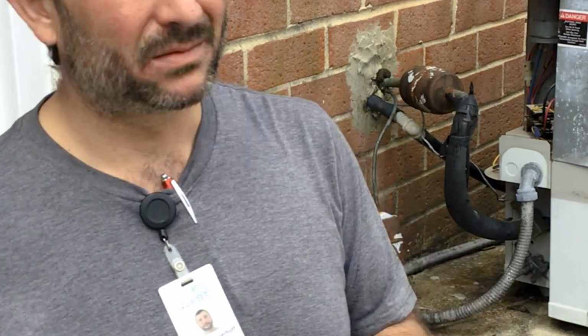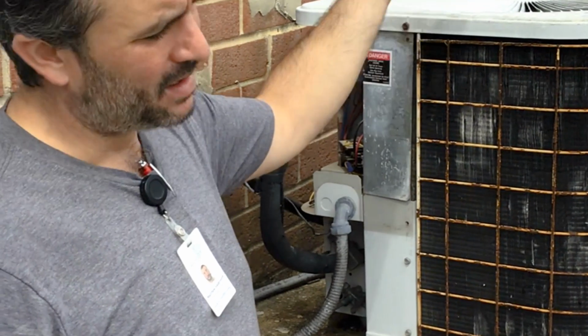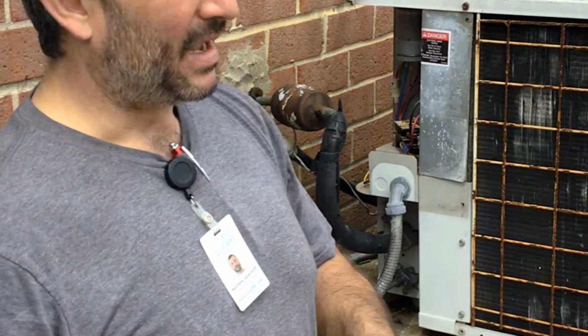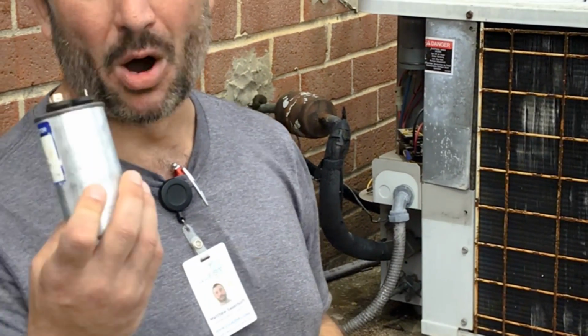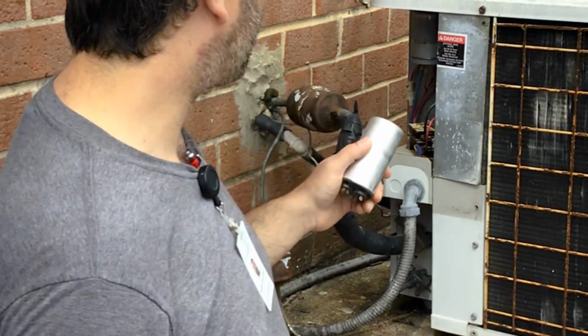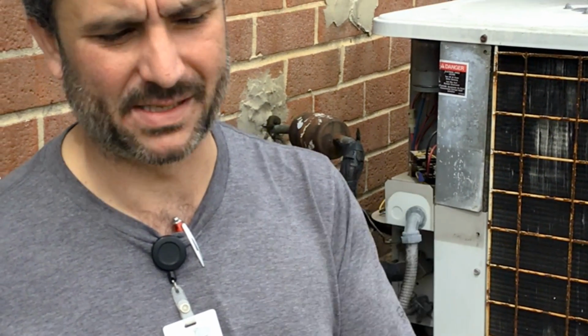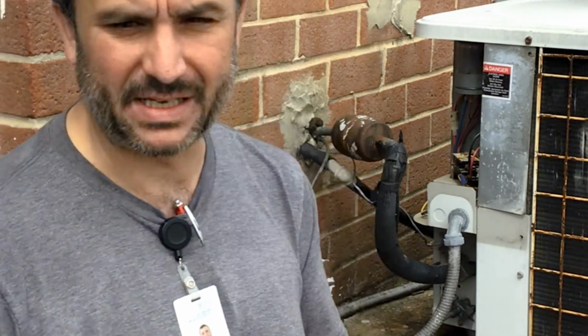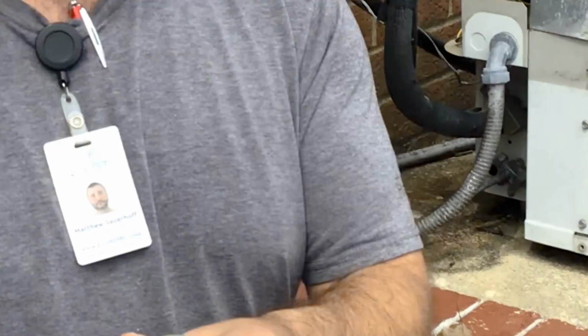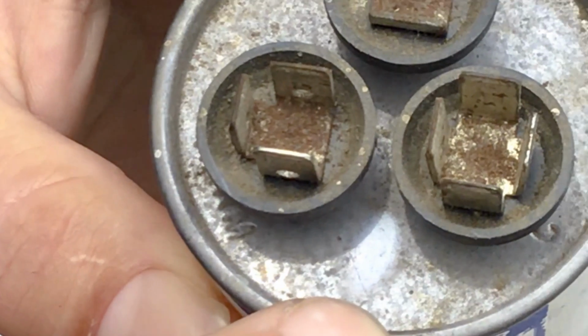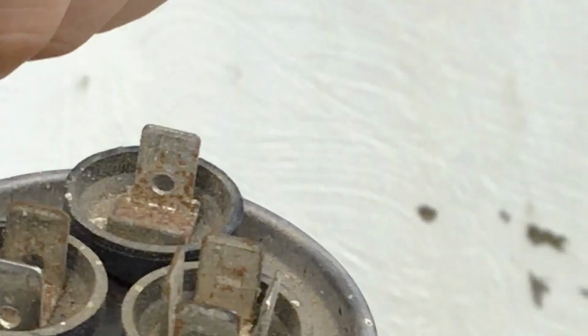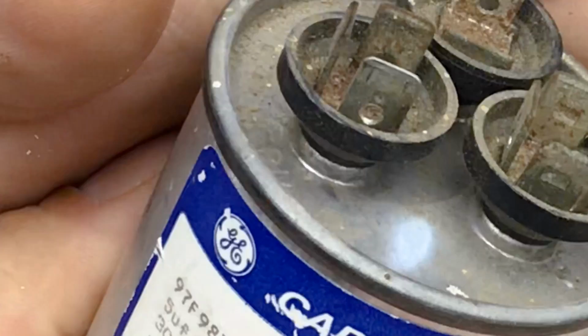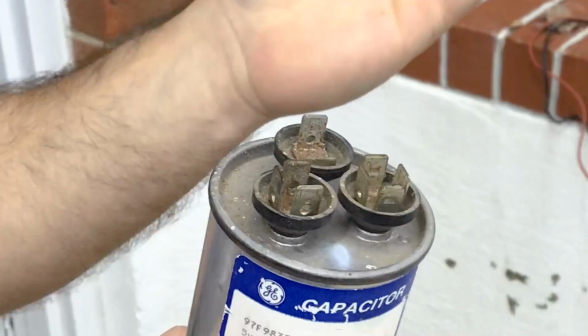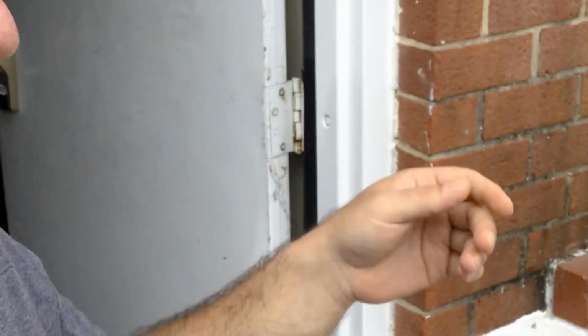If you guess wrong and your fan motor is bad, or your compressor is bad, and you wind up having to replace either one, you should always replace the capacitor anyway. So if something's not operational, it's always a good rule of thumb to just start with replacing the capacitor. A lot of times you can look at it, a visual inspection, and tell if it's bad. So here's a capacitor. You'll see a burnt white spot. Anytime you see that, this thing's fried. Most of the time, the top will bubble out. If you see it's convex like this, it's bad, change it. A lot of times you'll get lucky and then your fan will come on, or your compressor. A lot of times that was the problem.